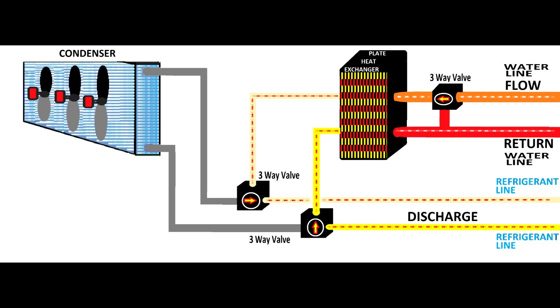It will be circulated through a heat exchanger inside the store, which serves as a desuperheater, and will recover that energy. And this is a fantastic kind of discovery, and whoever thought about this is a hero, because we can save a lot of energy. However, we don't have to take more than the refrigeration equipment gives us. Otherwise, we can lower the refrigerant pressure too much, and we can have some nasty surprises.